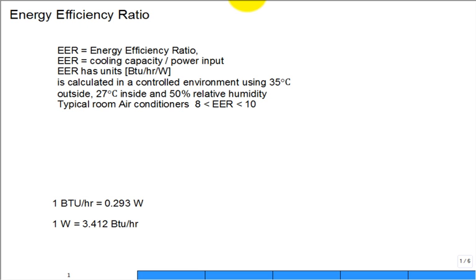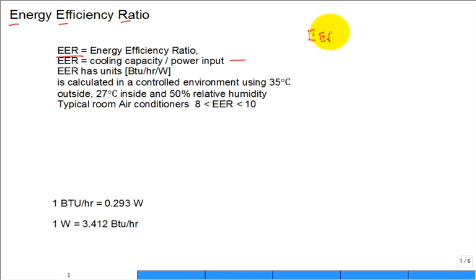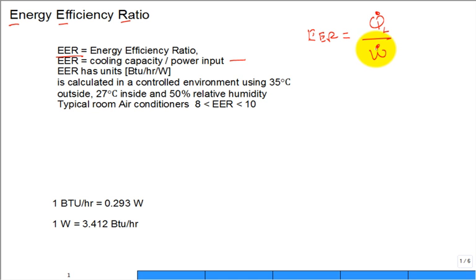I want to spend a little time talking about the Energy Efficiency Ratio — it has the acronym EER. It's defined as the cooling capacity divided by the power input, so the EER equals Q̇L, the heat removed from the low-temperature source in a refrigeration application, divided by Ẇin, the power coming into the system.